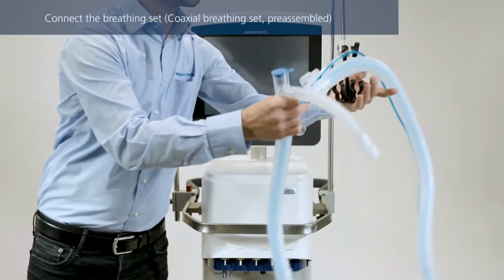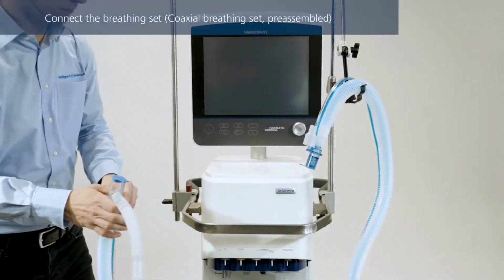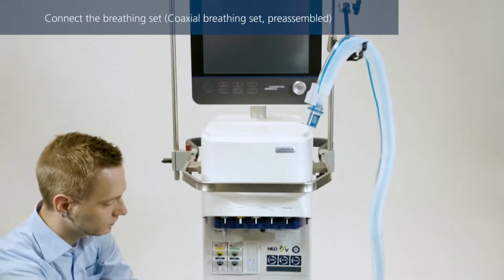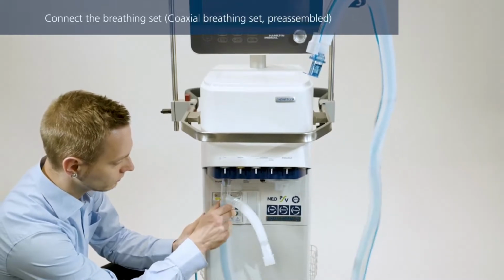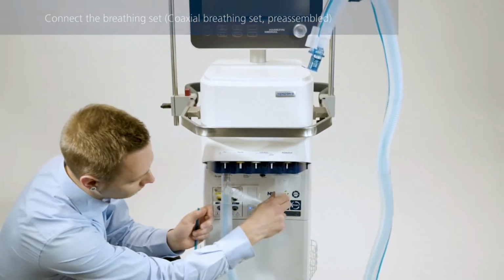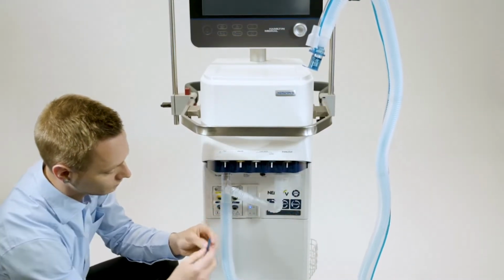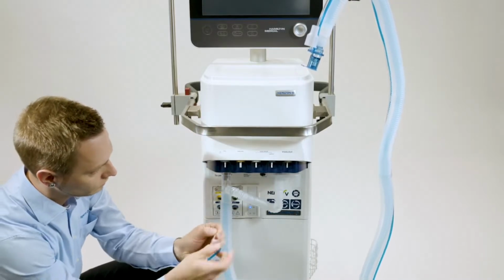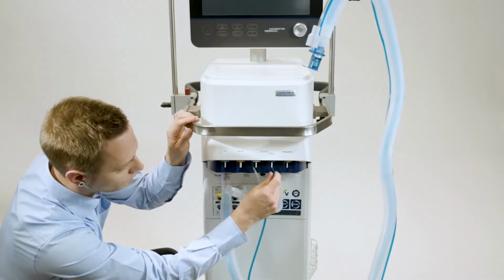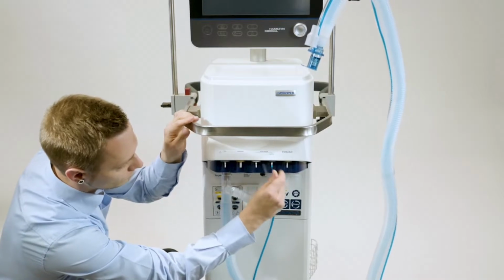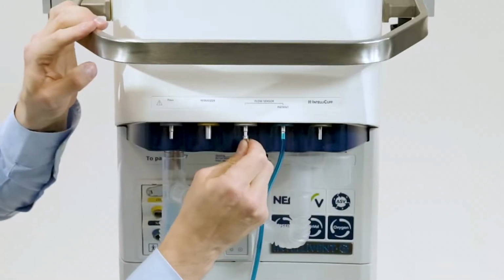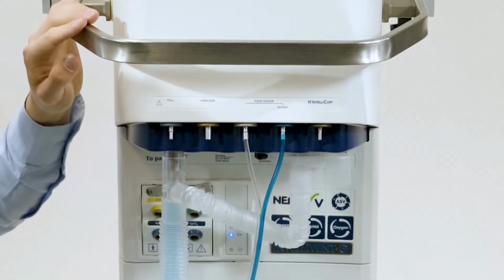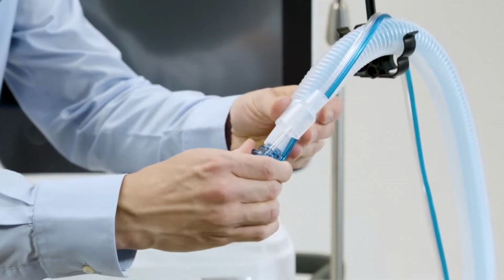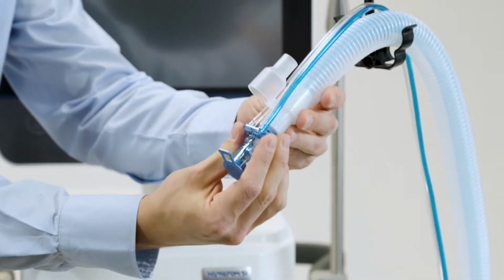To connect the coaxial breathing circuit, first attach the main tube to the inspiratory port, and then connect the expandable expiratory tube to the expiratory valve. Finally, attach the blue and clear tubes to the flow sensor connection ports on the ventilator. Always position the flow sensor tubing on top of the flow sensor.